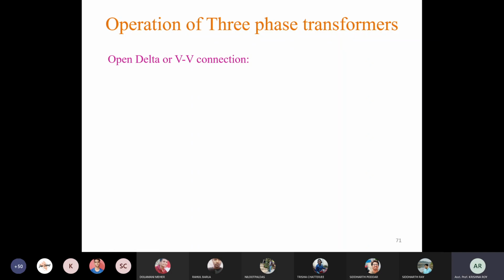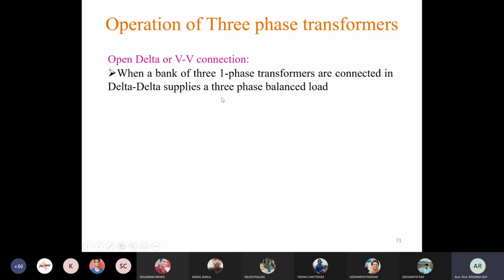Okay, open delta or VV connection. So what is this open delta? Let us see. When a bank of three single phase transformers connected in delta delta supplies a three phase balanced load, then each transformer carries 1/3 of the total load. Okay, so here the connection is delta delta. So we are using a bank of three single phase transformers, not a single unit of three phase transformer. So in this case each transformer will carry 1/3 of the total load.